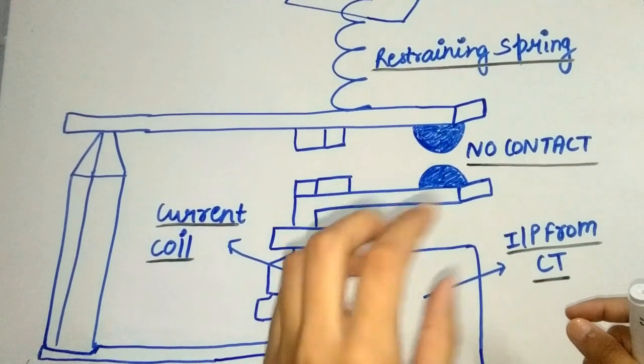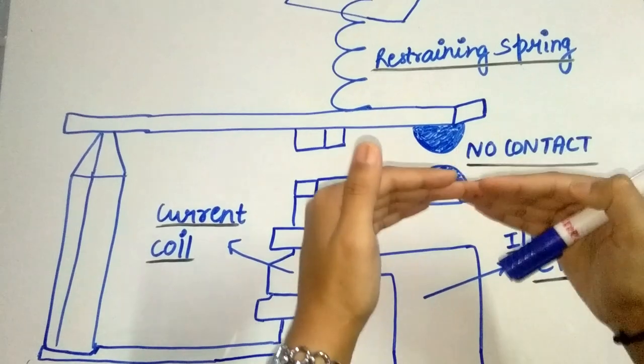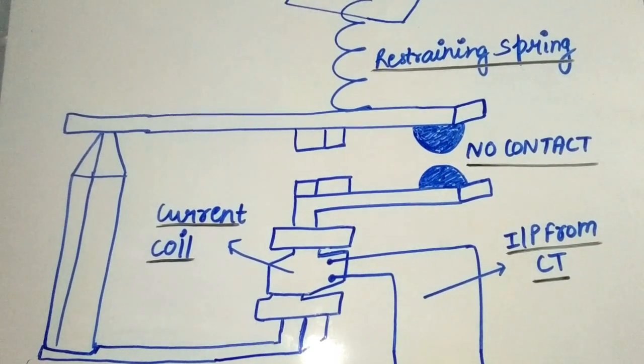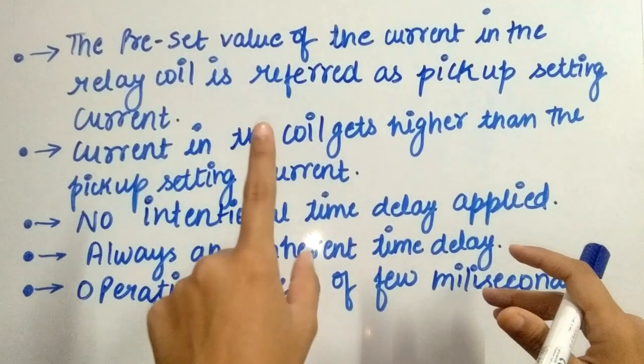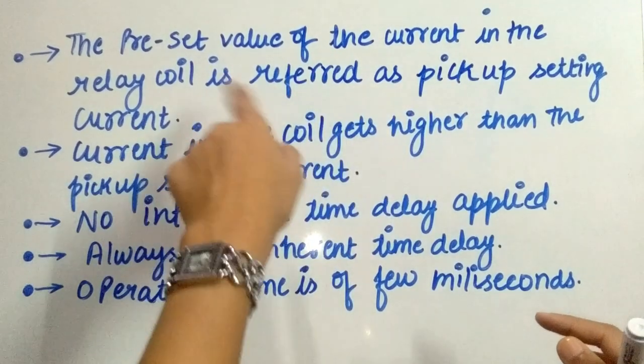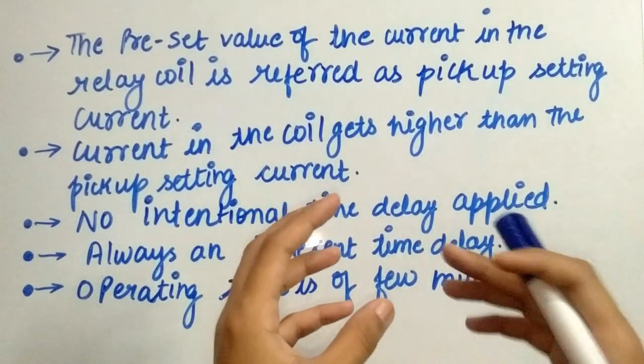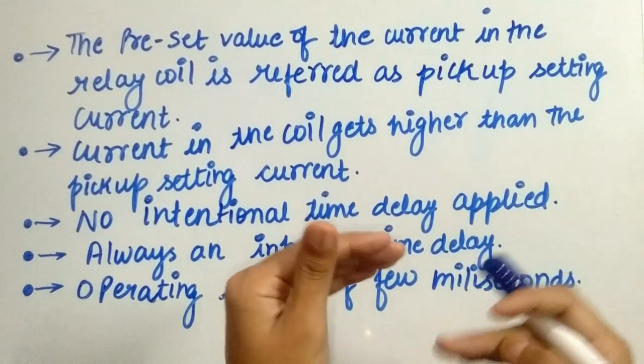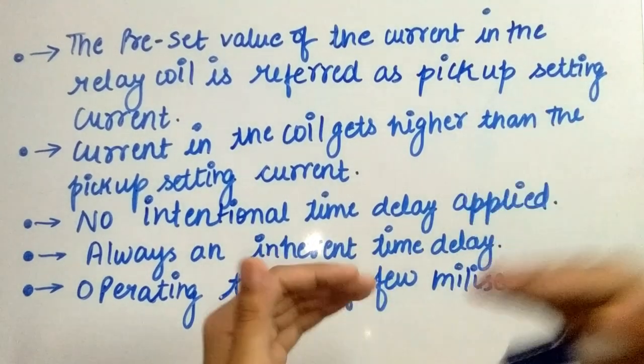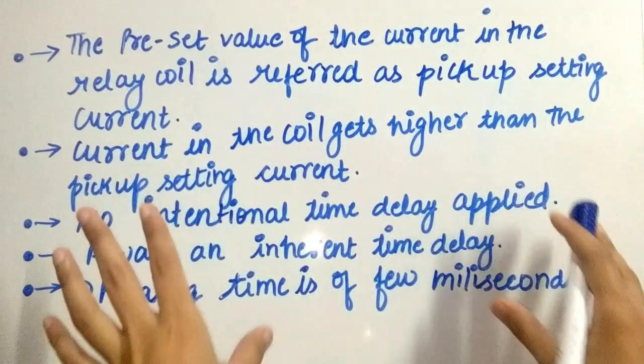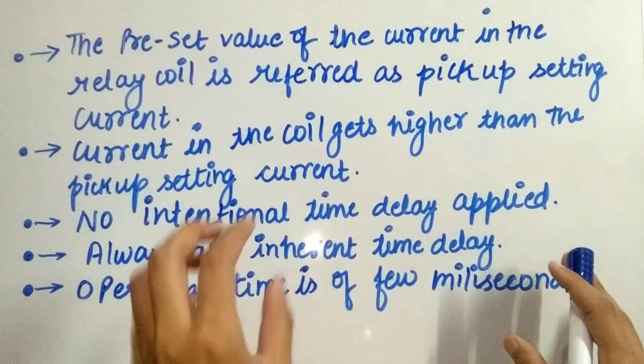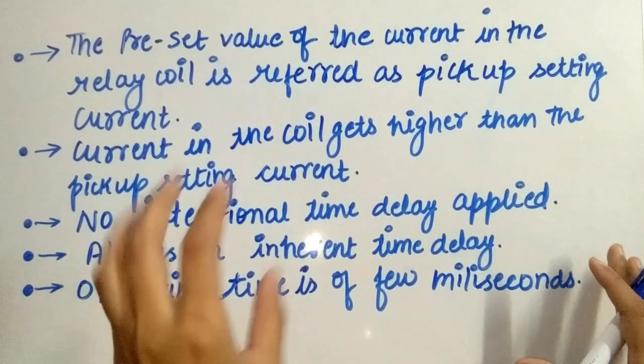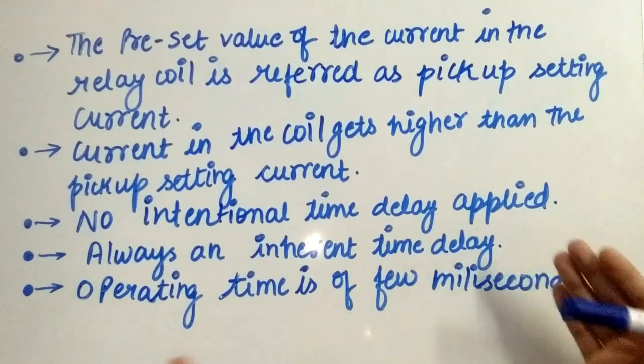The attractive force becomes enough to pull the iron piece towards the magnetic core, and as a result the normally-open contacts will close. The preset current value in the relay coil is referred to as the pickup setting current. The relay operates as quickly as possible — as soon as the coil current exceeds the pickup setting current, the relay operates. No intentional time delay is applied, but there is always an inherent time delay which we cannot avoid practically. In practice, the operating time of an instantaneous relay is a few milliseconds.